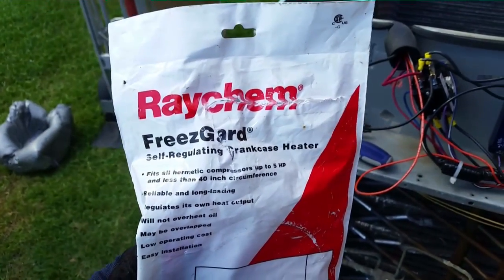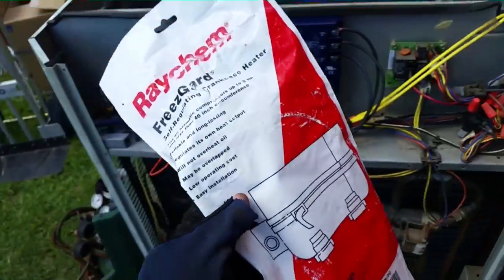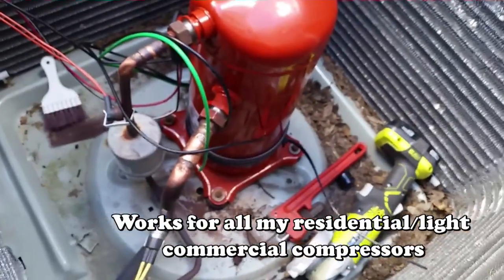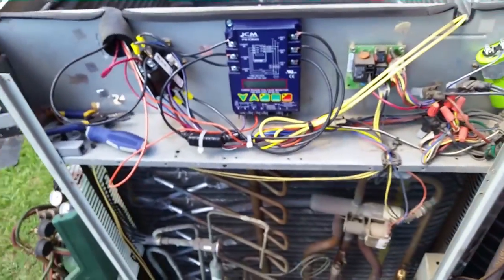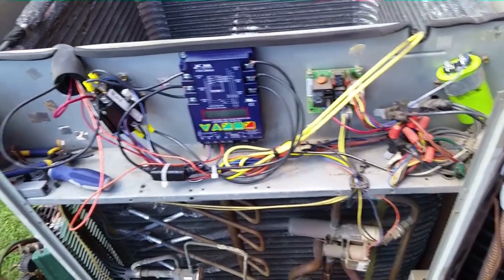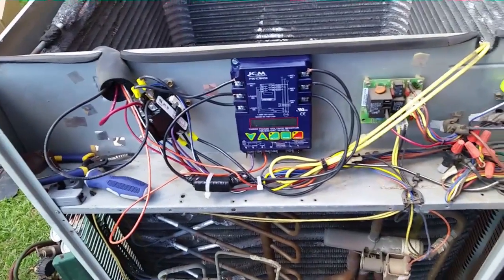I have my Raychem FreezGard self-regulating crankcase heater here. It can be overlapped because it comes very long, and there it is — you can see it down there on the compressor. I've overlapped it a couple times and wrapped it around there. It has a Panduit strap that keeps it tight, and you cut it off. I'm going to wire it to the bottom of the contactor so it's always on. We're about to pull a vacuum — I wanted to wrap that on there before I forgot.